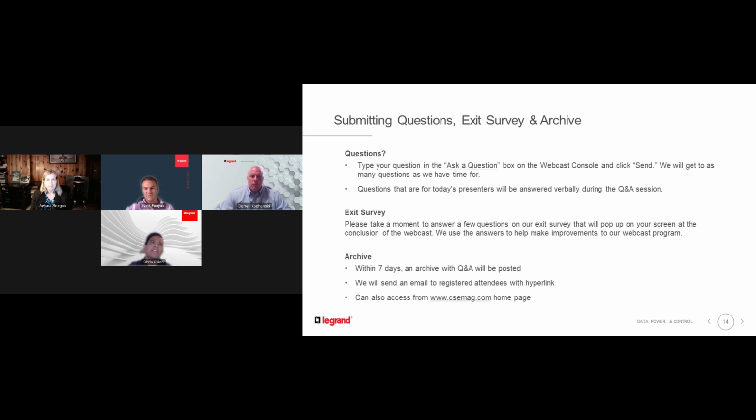Yeah, we often see requests to add more power to a particular run. And in some cases, like in a retrofit situation, we could break a run in half and then feed another end feed on the opposite side, essentially doubling the power of that row. So there's opportunity there where you can actually increase the power at that point. And we've seen requests like that over the years, especially if it's an older data center. Yeah.